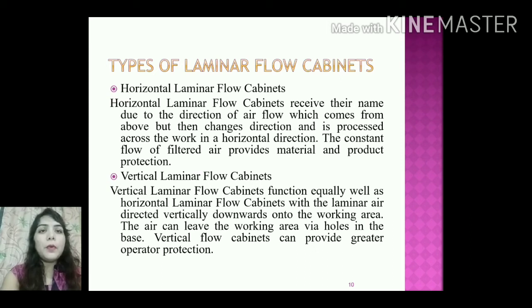The second type of laminar airflow cabinets is vertical laminar flow cabinets. Vertical laminar flow cabinets function equally as well as horizontal laminar airflow cabinets, with laminar air directed vertically downwards onto the working area. The air can leave the working area via holes in the base. Vertical flow cabinets can provide greater operator protection as air comes from ceiling to the floor.